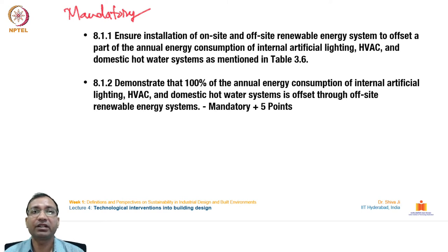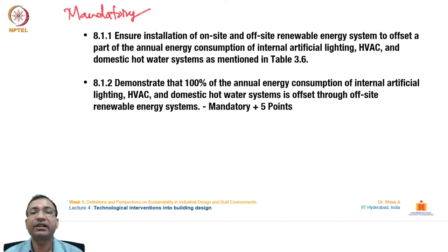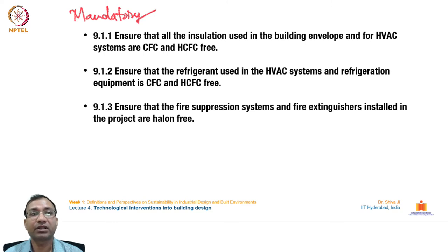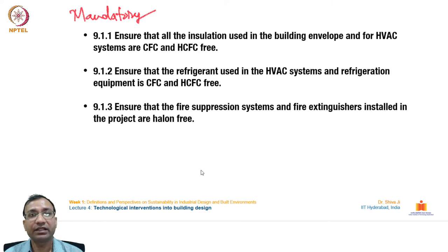Further mandatory energy criteria include: installing on-site or off-site renewable energy systems to offset part of annual energy consumption for internal artificial lighting, HVAC, and domestic hot water; ensuring all insulation in building envelope and HVAC systems is CFC- and HCFC-free; ensuring HVAC refrigerants are CFC- and HCFC-free; and ensuring fire suppression systems and extinguishers are halon-free, protecting the ozone layer.